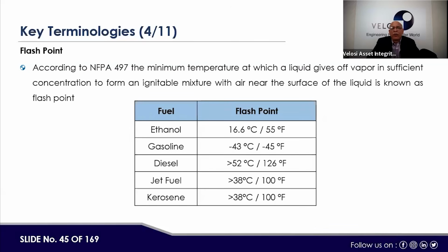Similarly, the flash point, according to NFPA 497, is defined as the minimum temperature at which a liquid gives off vapor in sufficient concentration to form an ignitable mixture near the surface of the liquid. For example, for ethanol it is 16.6 degrees Celsius. So it means that if a normal drinking alcohol, even a beer or whiskey, has a higher content of ethanol, it may catch fire.